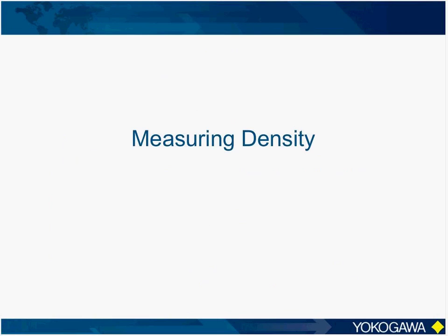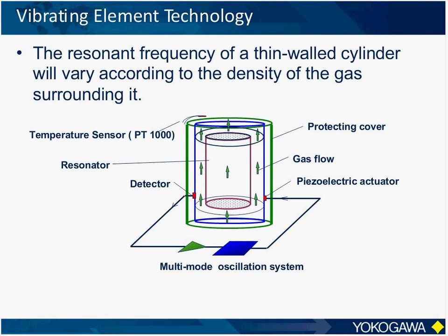Now we'll discuss the primary measurement of the vibrating element, which is what we had said earlier is gas density. And here we have a very basic illustration of the vibrating element detector. It's comprised of a cylinder, which is the resonator, within another cylinder, and all of this is inside a protective cover. Now the gas being measured is introduced and flows between the two cylinders, and a piezoelectric actuator forces the resonator to vibrate. And the resonant frequency at which the cylinder vibrates is going to be dependent on the density of the gas that is surrounding it. Now, this frequency is measured by the detector and transmitted to the analyzer, which then calculates the gas density based upon that frequency. Now, you'll also notice a temperature sensor within the gas stream that is also used for real-time compensation.